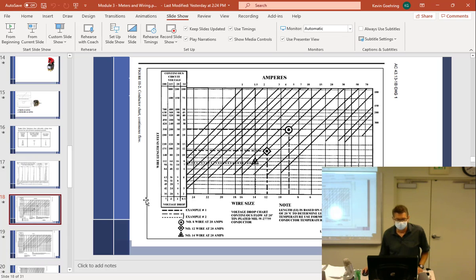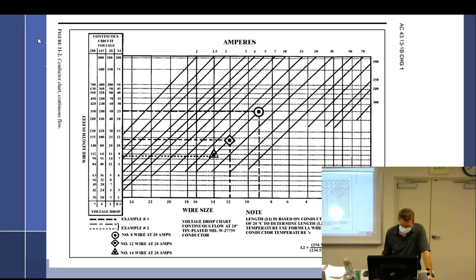Well it's kind of the same thing. So what was the maximum length of wire? What is the maximum length of number 8 wire that can be used for a 28 volt system at 50 amps? I think we already did that, right? 50 amps, come down here, I have 28 volts, I have number 8 wire, it's here, so we go right there. We came over here, we had 30 feet.